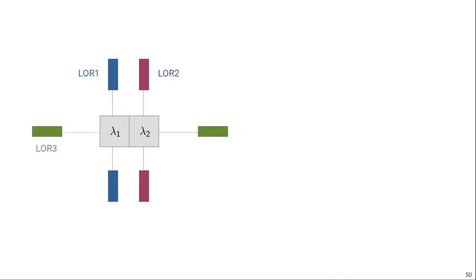Before explaining what we usually do instead, let's look at a short motivating academic toy example — actually one of the easiest reconstruction problems you can consider. We have an image with only two pixels or voxels: voxel 1 with unknown activity concentration lambda_1 and voxel 2 with unknown activity concentration lambda_2. We also have a very simplistic PET scanner with three detector pairs: the blue one called line of response 1 (LOR 1), the pink or purple one which is LOR 2, and the green one which is LOR 3.